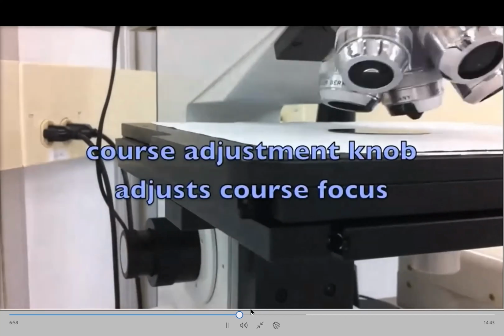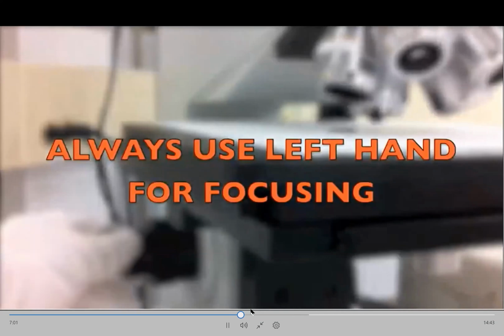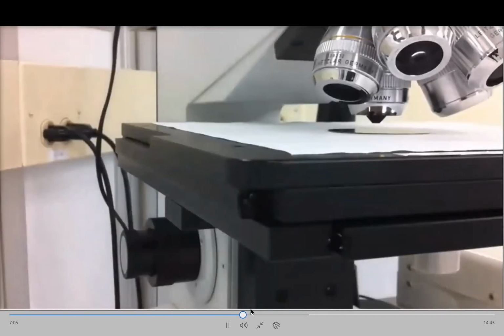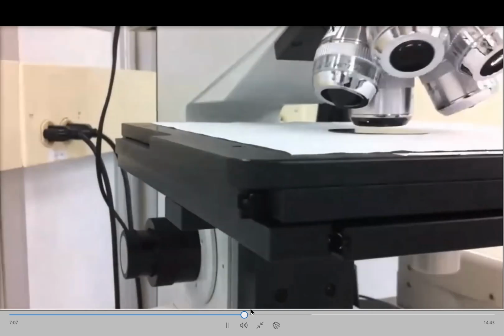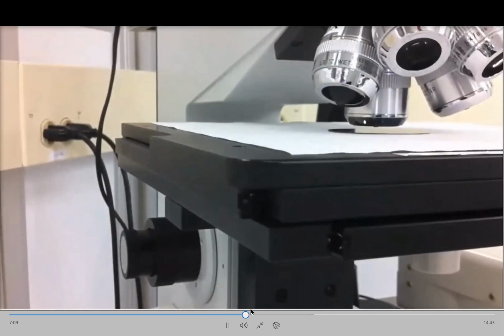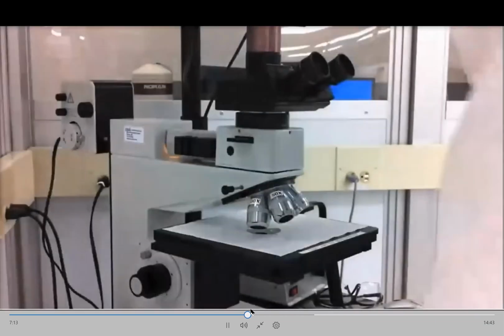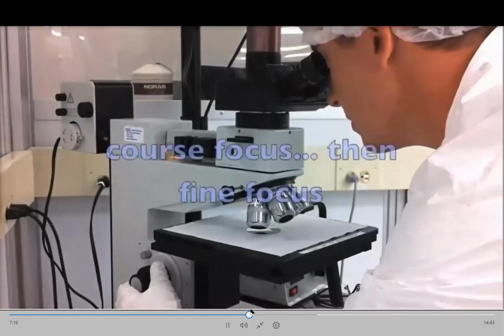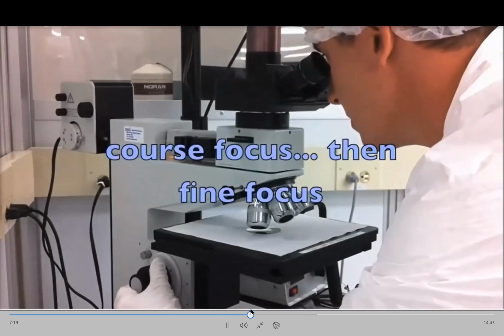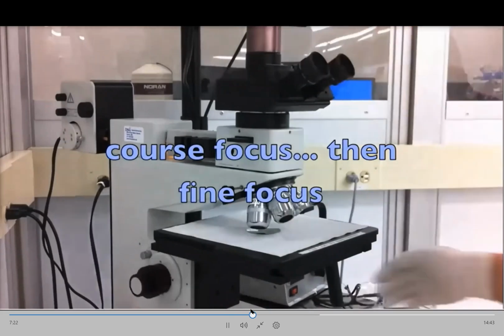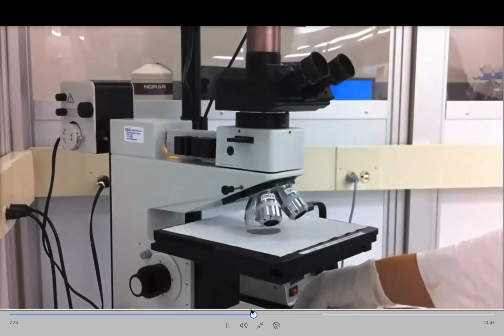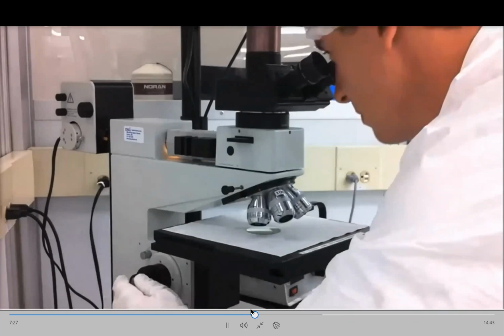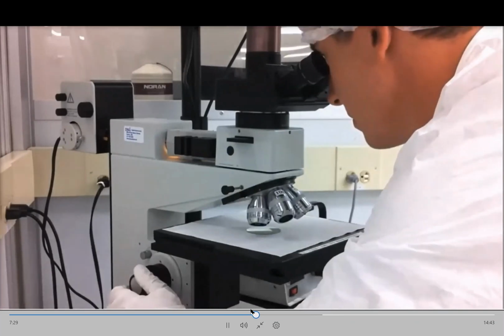Notice that we always use our left hand for focusing, as this will avoid bumping the stage and otherwise interfering with proper tool operation. When imaging a sample, always begin at the lowest magnification and then adjust coarse focus. After this, use the fine focus knob to more precisely focus your image. Once this is done, rotate to higher magnifications and then adjust fine focus as needed. As you continue to increase the magnification, it will also become necessary to increase the light source intensity.